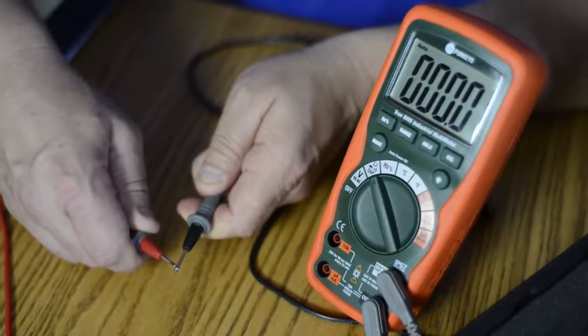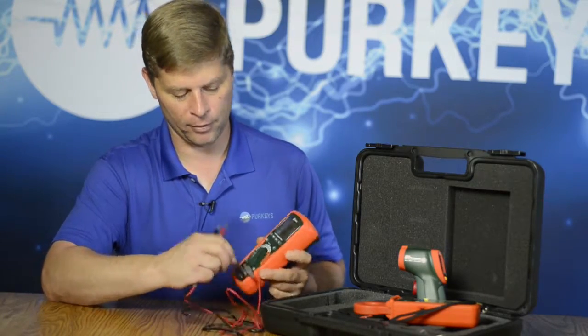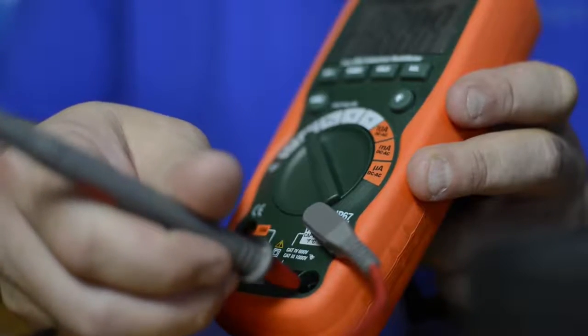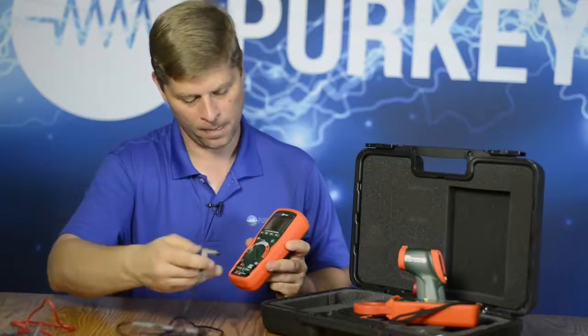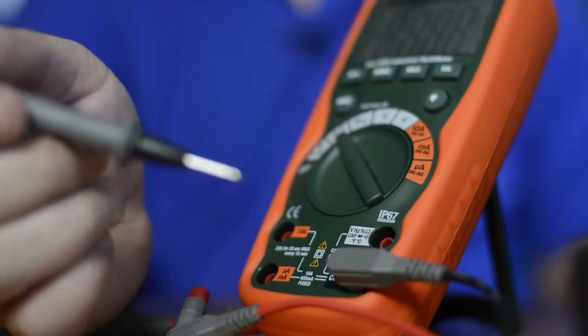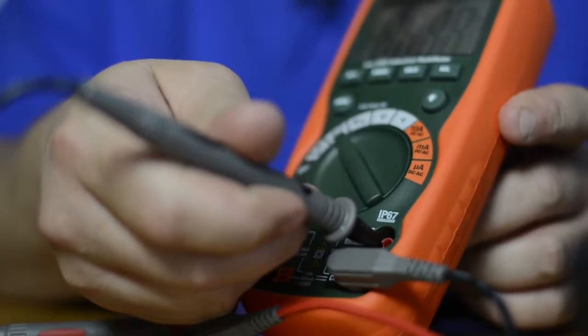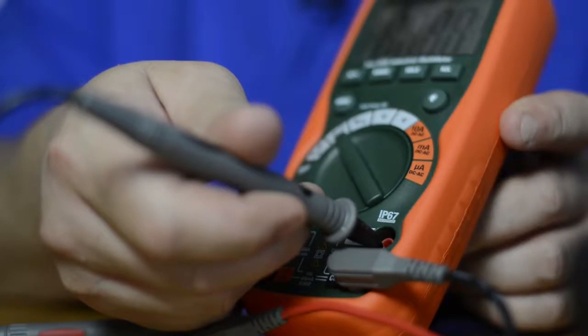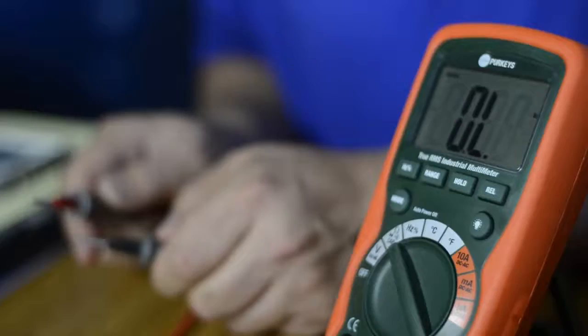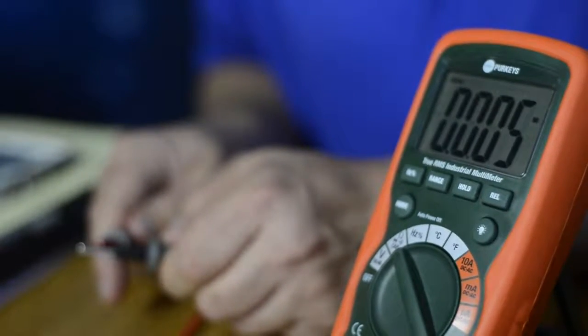We want to check them individually. So we're going to take the black lead out first, insert just our red lead in here. Now we're going to check just the black lead. And we know our black lead is good. So everything checks out. I know the meter leads are good, and as far as the ohm function, I know it is in calibration and I did zero out.